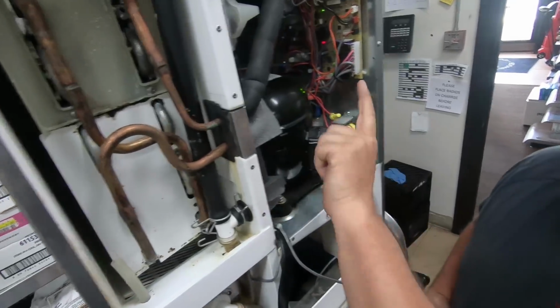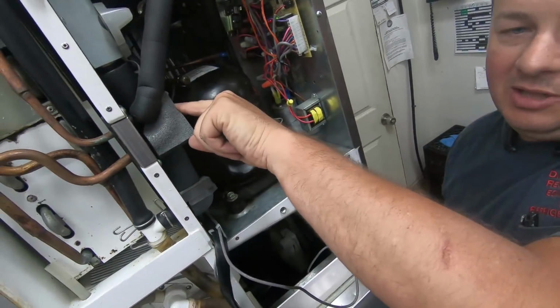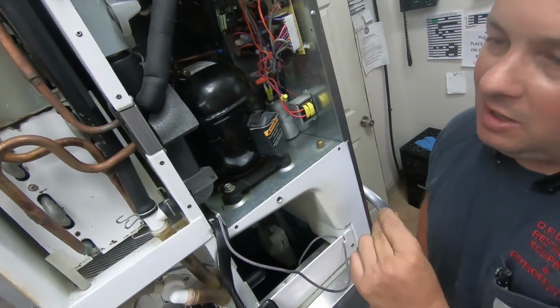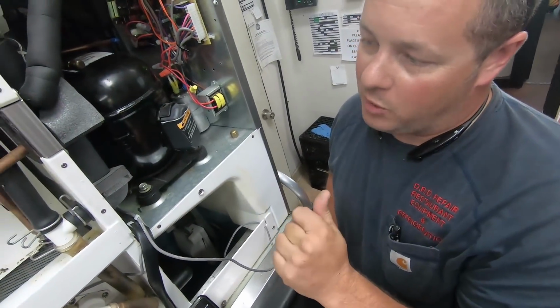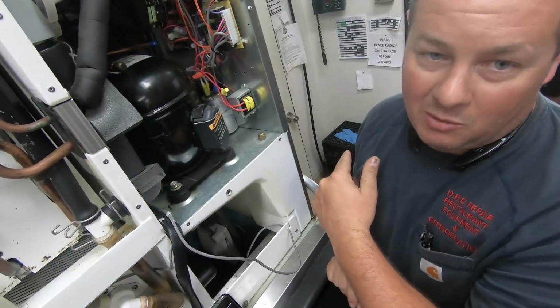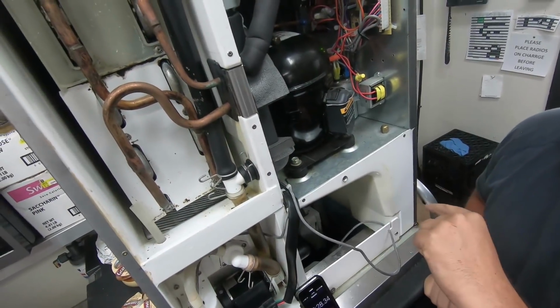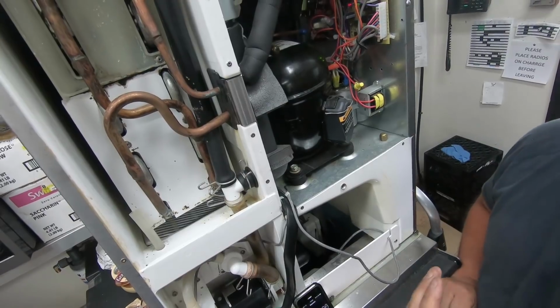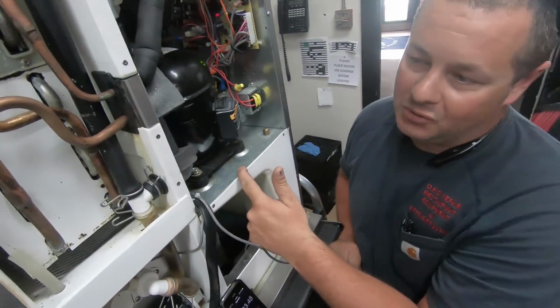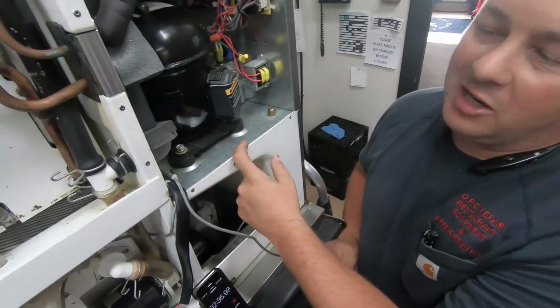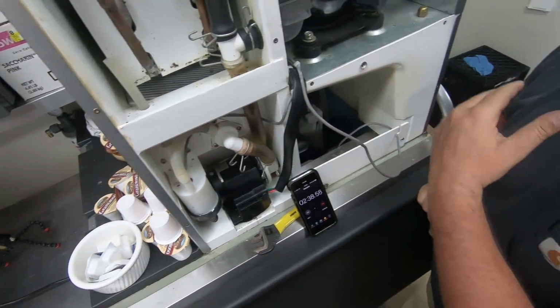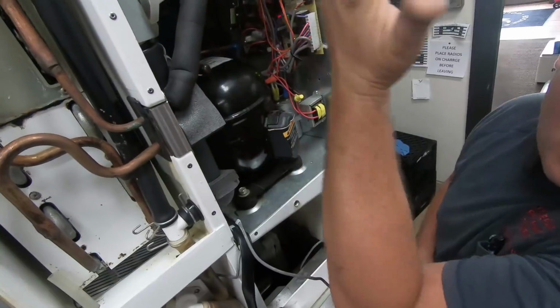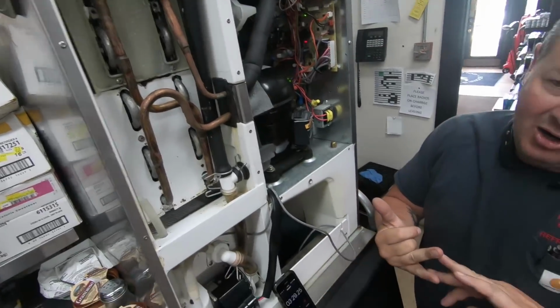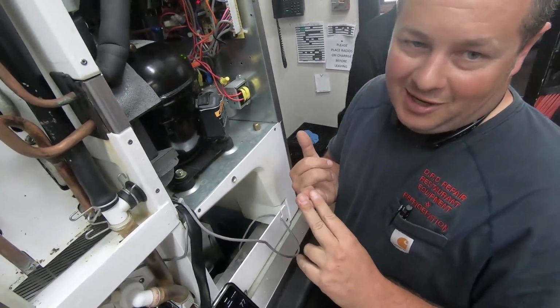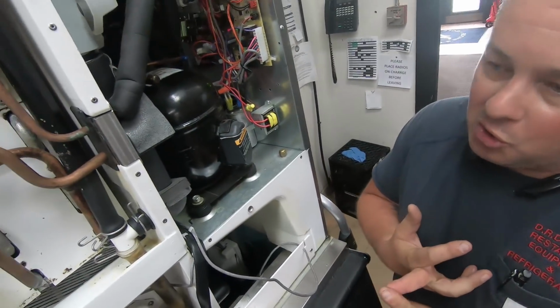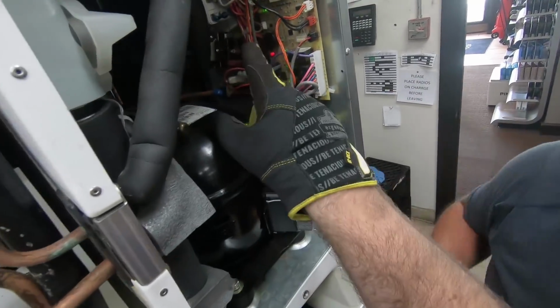On Hoshi's, there's a thermistor right in here on the suction line, 48 degrees. Once the thermistor hits 48 degrees, it initiates a timer sequence on the control board for how much longer to run. This machine's default was 90 seconds. I changed it to 180 seconds, which you just do on the dip switches on the board. Things that you can change are how long the harvest is, and then you can also change the purge cycle. So all on the dip switch settings? All on dip switches.